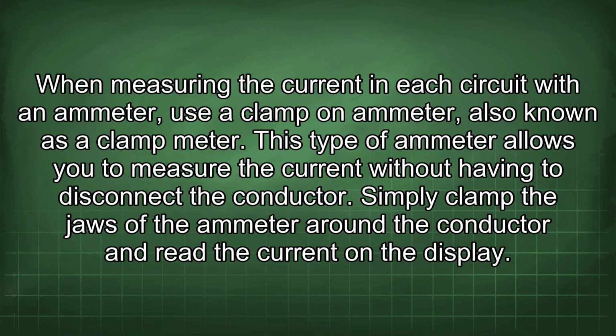When measuring the current in each circuit with an ammeter, use a clamp-on ammeter, also known as a clamp meter. This type of ammeter allows you to measure the current without having to disconnect the conductor. Simply clamp the jaws of the ammeter around the conductor and read the current on the display.